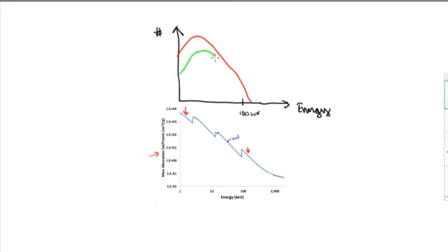If you look, this actually changes the quality of the spectrum. If I were to calculate the mean energy of these photons, for the red curve as it enters, it would be somewhere here, let's say. And then for the spectrum as it exits, the mean energy might be, let's say, up here. So you'll see that the mean energy is increasing, and this is referred to as beam hardening. Hardening means that the mean energy goes up. That's an important concept. It's true of really any material that the photons pass through.